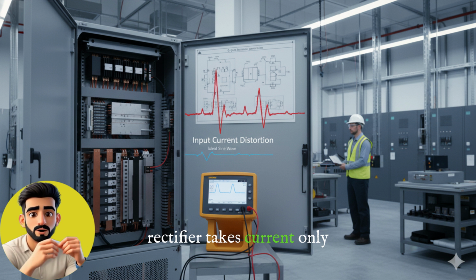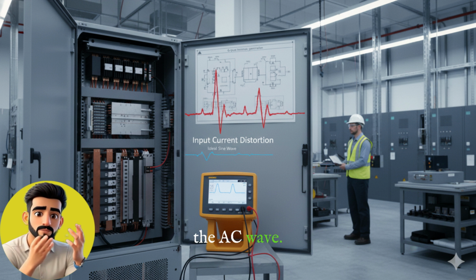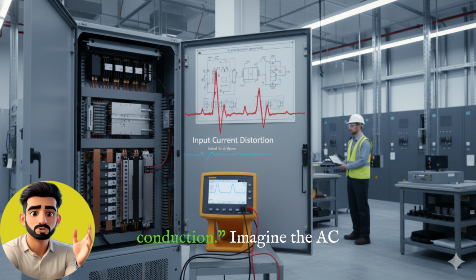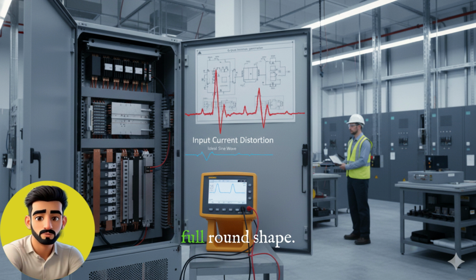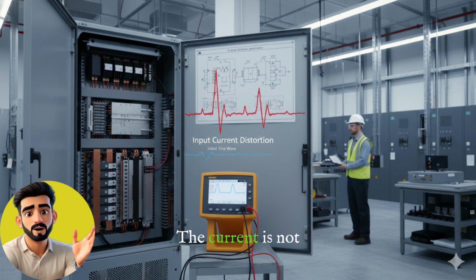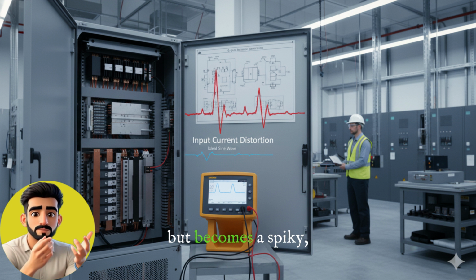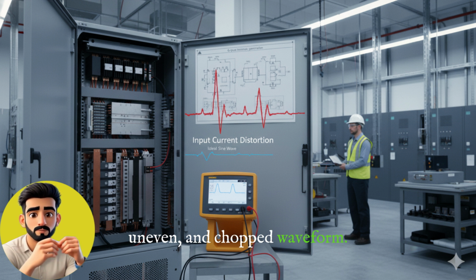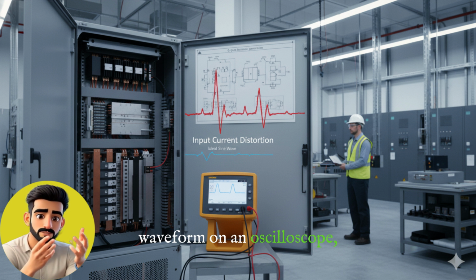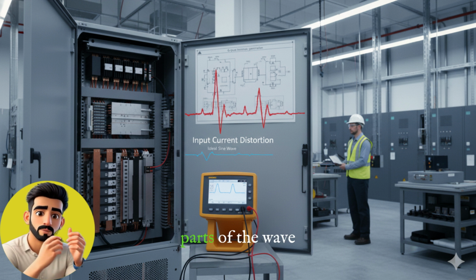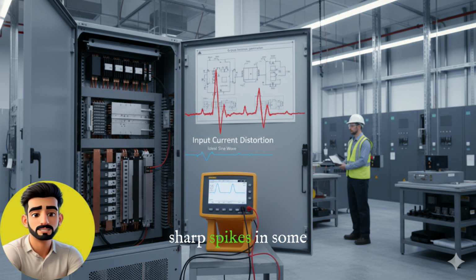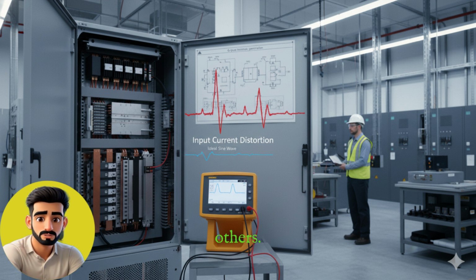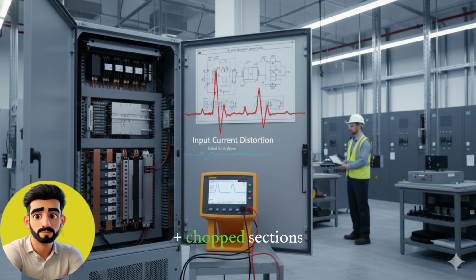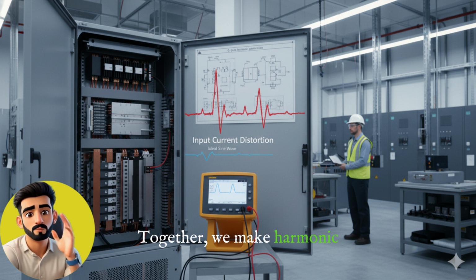The rectifier takes current only from specific portions of the AC wave. We call this selective conduction. Imagine the AC wave coming in a full round shape, but the rectifier only picks the top portions of that wave, ignoring the rest. Result? The current is not a smooth sine wave, but becomes a spiky, uneven, and chopped waveform. When you view this waveform on an oscilloscope, you will notice some parts of the wave are missing. There are sharp spikes in some places, deep notches in others. These spikes plus notches plus chopped sections, together, make harmonic currents.